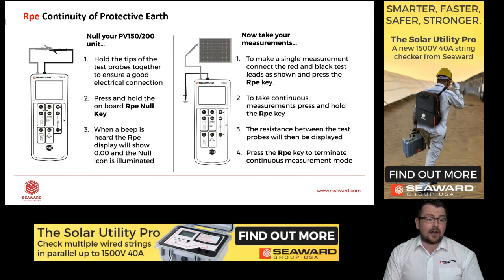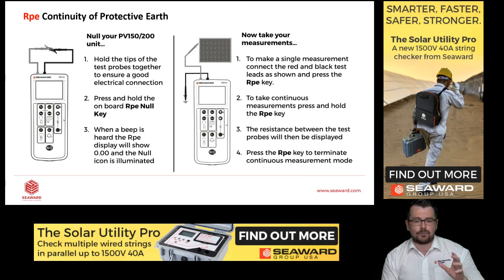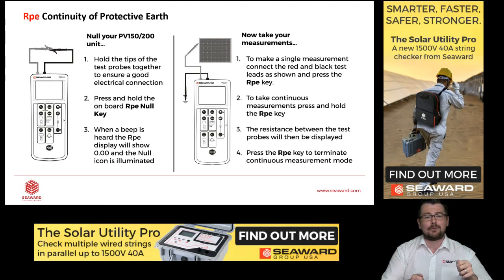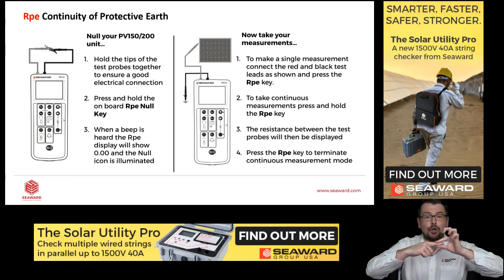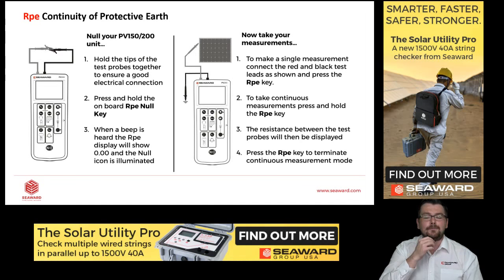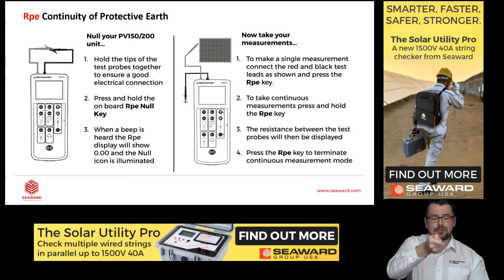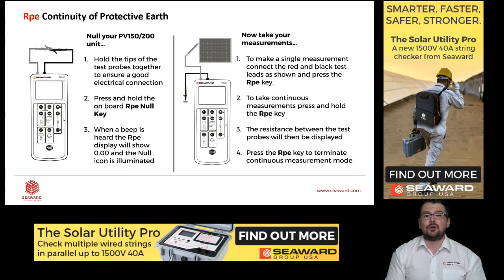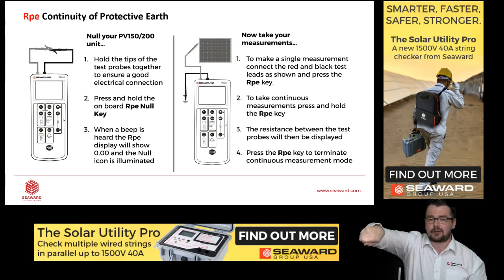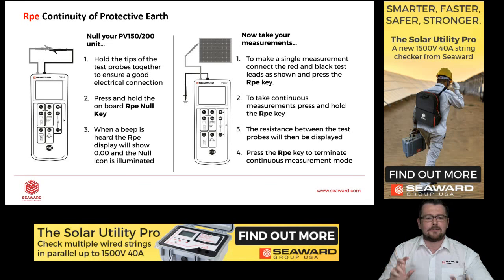So with the PV150 and the PV210 and the 200, you can actually perform the RPE test. Again, the instrument is handheld. You press and hold the RPE button with the black and the red cables connected. And first of all, we null those cables. So if there's any excess resistance inside, we've nulled that to 0. And then it's very easy. We connect to the ground, and then we use a point-to-point method to test the earth continuity. So this could be to the frame, to the backsheet, to the combiner, and we're just making sure that the path to earth is consistent throughout the PV array.